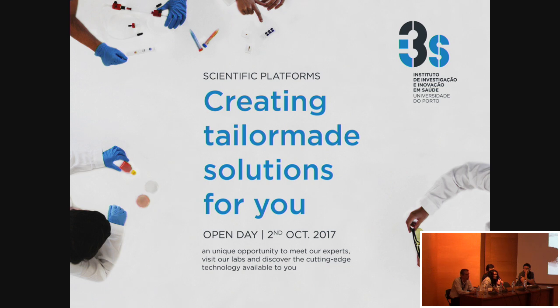Basically, I don't know if you do it with a colloidal tip or a pyramidal tip. If you do it with a colloidal tip, you can bind the colloidal tip. Otherwise, you need what we call a micro manipulator to make the tip. I don't know if that's the equipment that the EMEM group has. Here, we do not have that micro manipulator. We can buy the colloidal tips, but we don't have the micro manipulator tip.